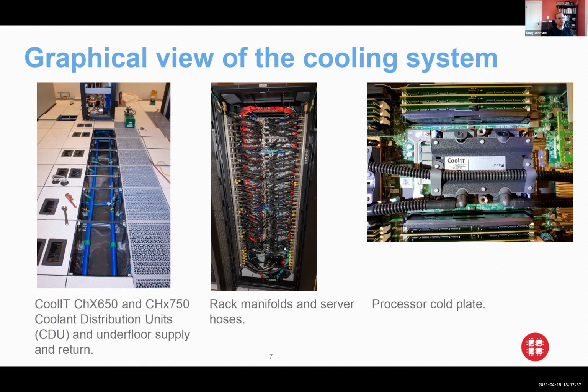There's a bit more to work around, and you have to be more careful so you still have a manageable server install. Even though OEMs have these as supported products, it's very easy for the final integration they build and design to result in cable or hose runs that make it impossible to work on. So there's some upfront cost in paying more attention to the physical layout in the rack and making sure everything works right. Then ultimately you get into the server and the specially designed cold plates for the processors they support, replacing the heat sink, and also importantly, removing the need for some of the airflow in the system.